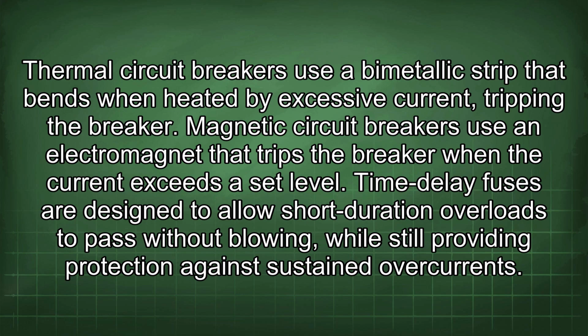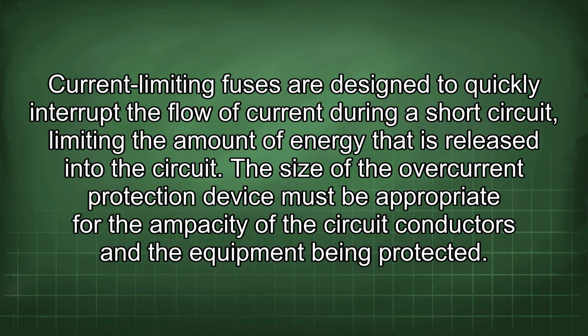Time delay fuses are designed to allow short-duration overloads to pass without blowing, while still providing protection against sustained overcurrent. Current-limiting fuses are designed to quickly interrupt the flow of current during a short circuit, limiting the amount of energy that is released into the circuit.